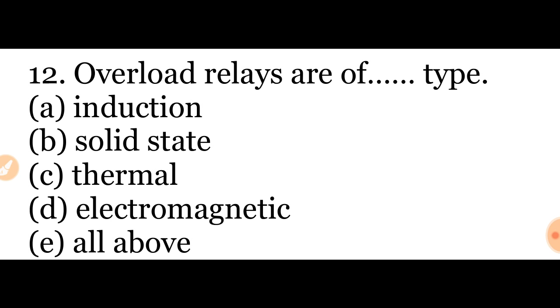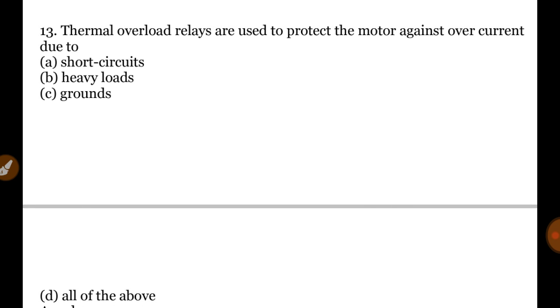Overload relay are of the type induction, solid state, thermal, electromagnetic, all of the above. Answer is all of the above. Thermal overload relay are used to protect the motor against overcurrent due to option A, short circuit, heavy load, ground, all of the above. Answer is heavy load.